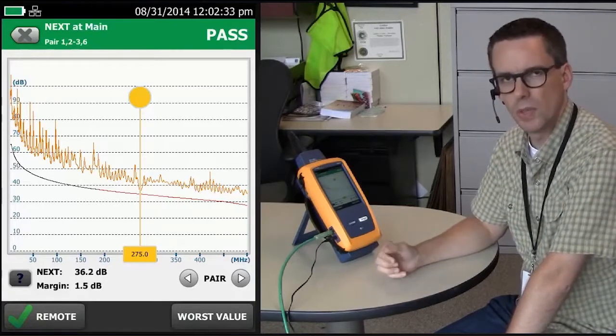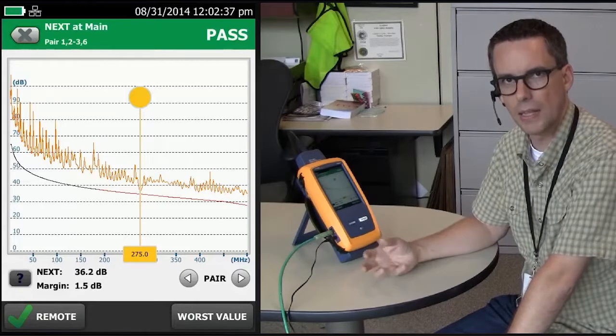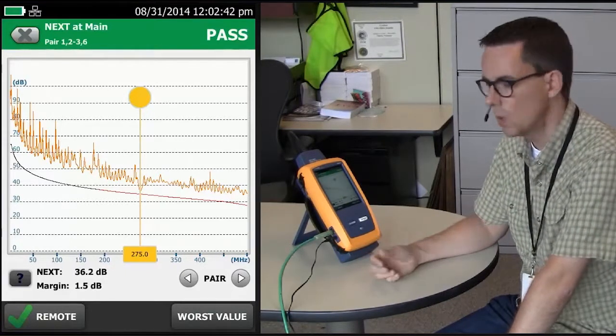What is the 4 dB rule? If the insertion loss of the pair is less than 4 dB, then that near-end crosstalk measurement is ignored.